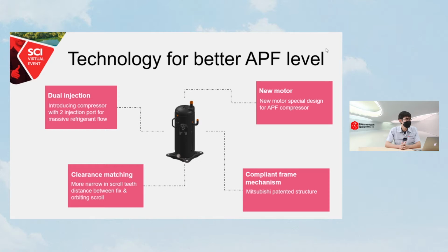And we have a dual injection, which is a compressor with two injection ports. With the two injection ports, our compressor can get a very massive refrigerant flow. And the clearance matching technique: the narrower the scroll tip distance between the fixed and orbiting scroll, the more refrigerant can flow in the system. And another one I am proud to present is the compliant frame mechanism, which belongs to a patent structure. Let's see how they work together.